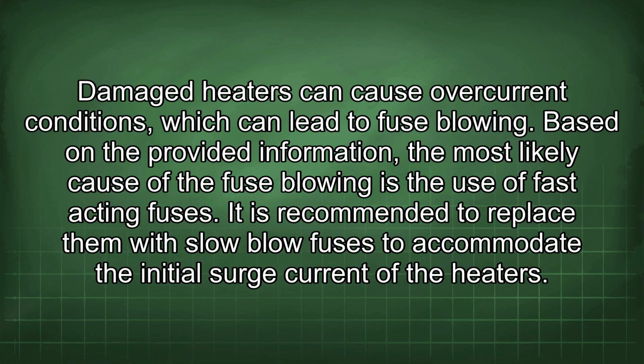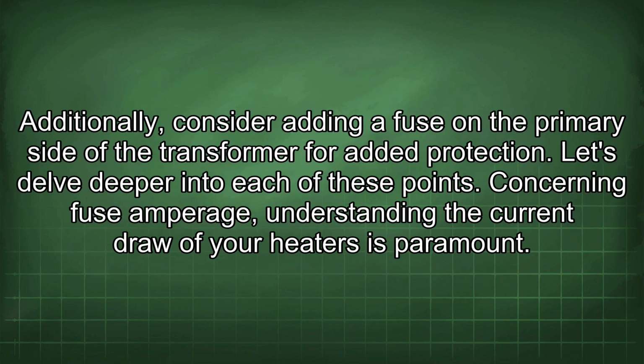Based on the provided information, the most likely cause of the fuse blowing is the use of fast-acting fuses. It is recommended to replace them with slow-blow fuses to accommodate the initial surge current of the heaters. Additionally, consider adding a fuse on the primary side of the transformer for added protection. Let's delve deeper into each of these points.